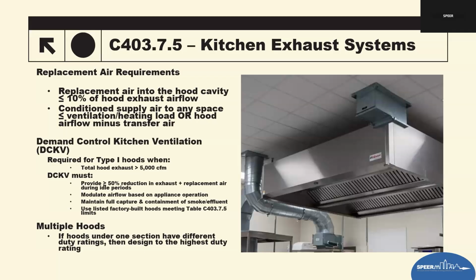And then field inspections: verify the DCKV sensors, such as temperature, optical, or IR, and make sure they're installed correctly. Confirm airflow modulation through trend logs or live BAS data. And then test that the idle reduction function is reducing airflow by that 50%. And then inspect the hood's label. Is it UL 710 listed? And lastly, verify airflow balancing matches the hood's duty rating. So is it meeting the larger of the two pieces of equipment?